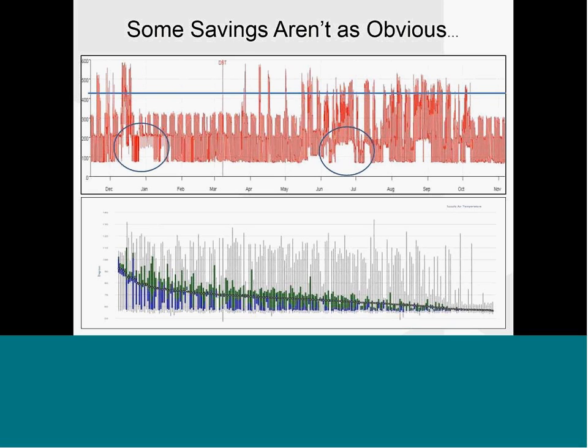I have that blue line up there, and that's kind of an arbitrary line of, hey, if we could keep those peaks down below 425, then we're going to save a lot of money. That's a pretty easy calc, and then you're using your technology to determine what level, what load, and what improvements we need to keep us below that 425, and then notify us as we're getting close so we can monitor the equipment. That's a great savings—if you have demand charges, there may be an area you can target within your portfolio to save consistent funds and maybe justify some equipment upgrades.